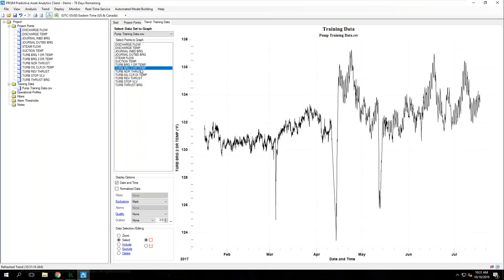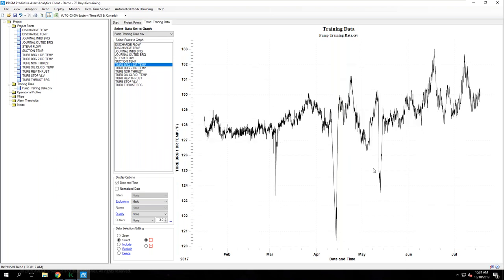Now, if I click through some of the other tags, you'll see that all of their profiles have been cleaned up as well. What we do in Prism to make the data cleanup process quick and easy is, when we delete data at a particular point in time, say March 1st at 12 a.m., we go through and delete the data for all of the tags in this predictive model at that same time. If you think about this equipment in a real life circumstance, when the pump is shut down or there's some anomalous condition, those conditions impact pretty much all of the tags at the same time. So we remove the data by time slice so you don't have to go through and manually clean up each tag individually, though you do have that option if you want it, generally it's not required.